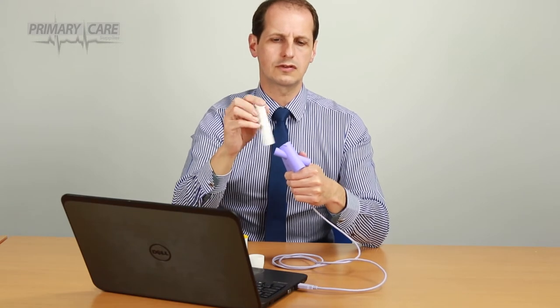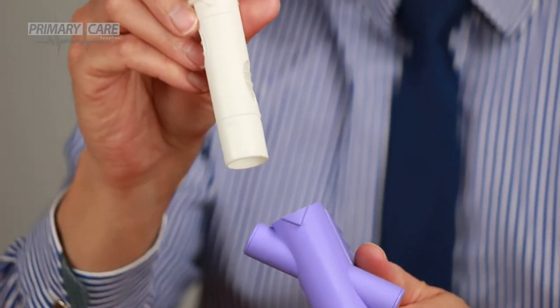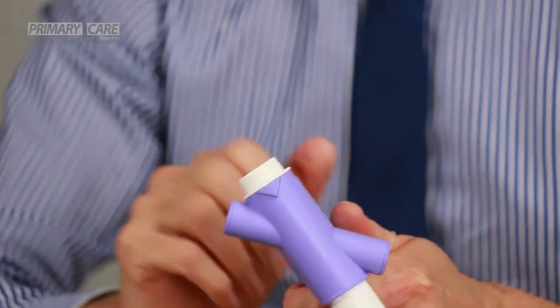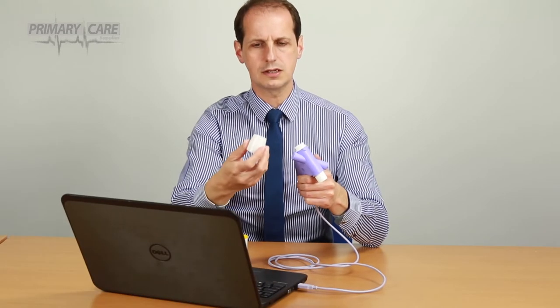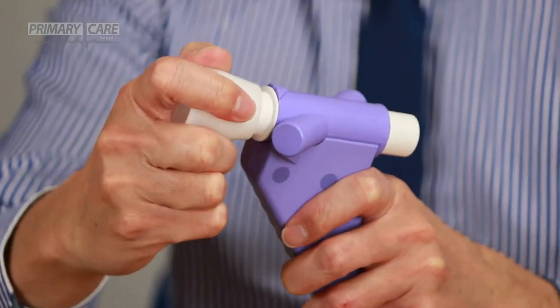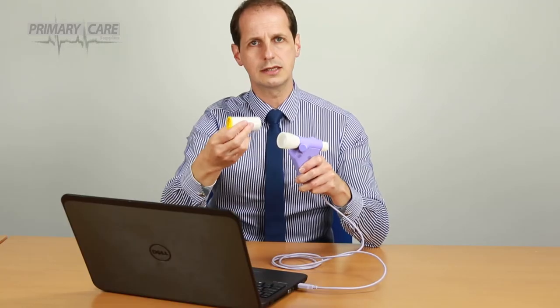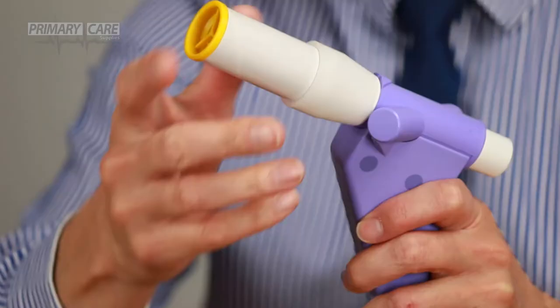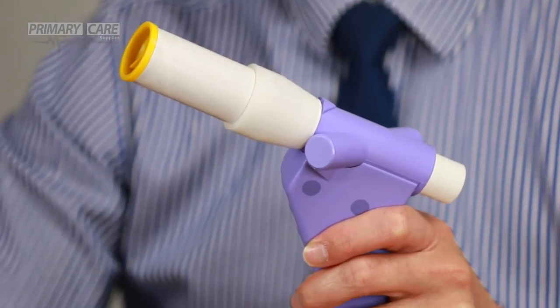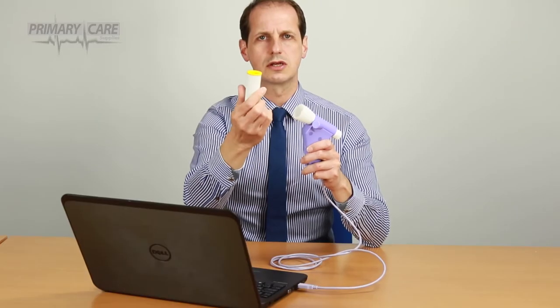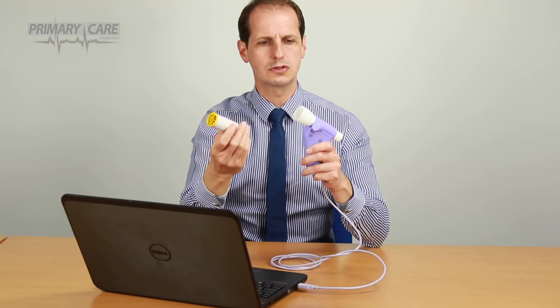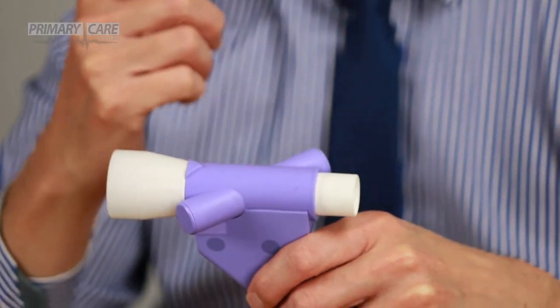To pop this in, you'll see there's a triangle on here and a triangle on the Spirette M. Push that in. Then onto the front goes a mouthpiece adapter. And then your standard spirometry cardboard mouthpiece will just go onto the front of that. So between each patient, you obviously change the mouthpiece because they're single patient use. And the Spirette M is changed on a weekly basis.